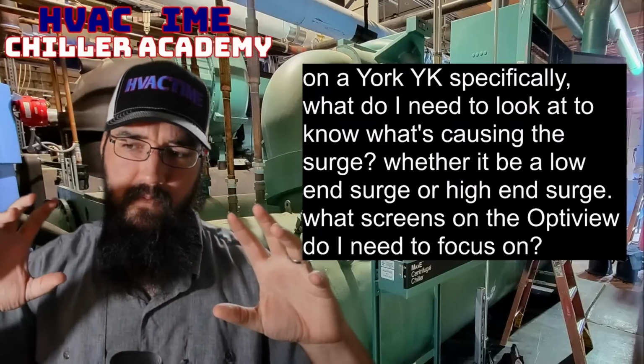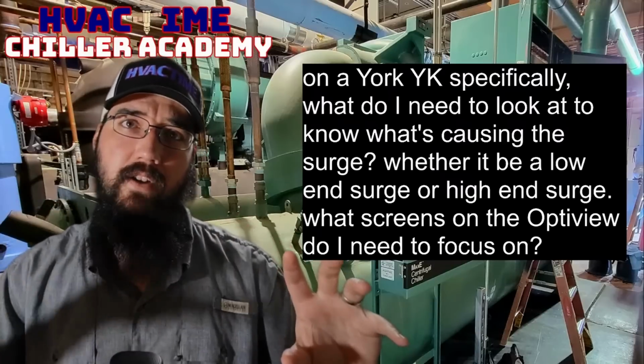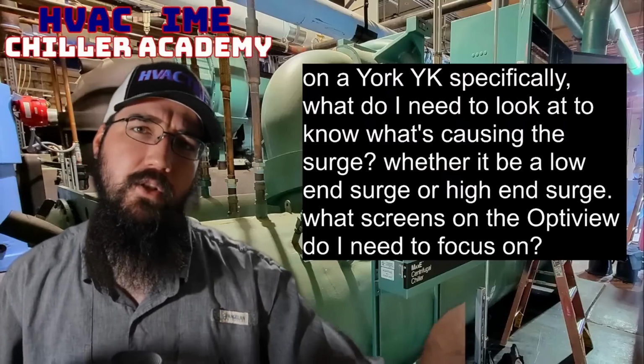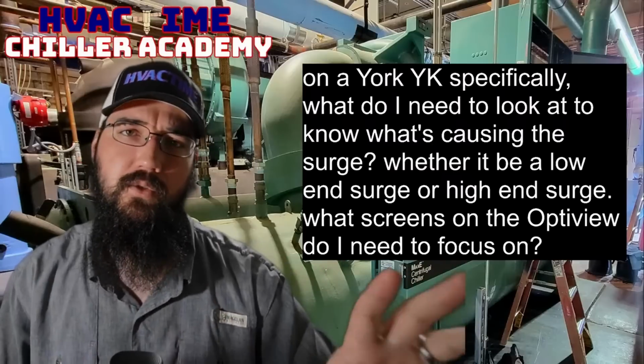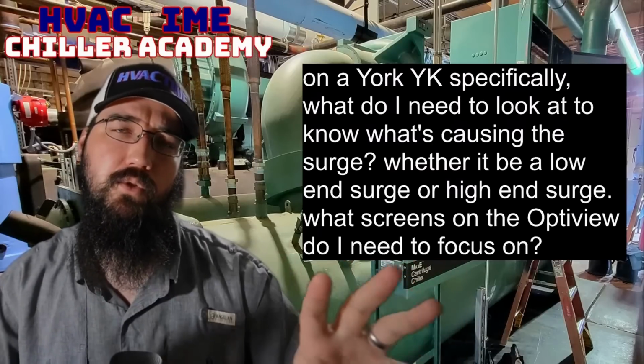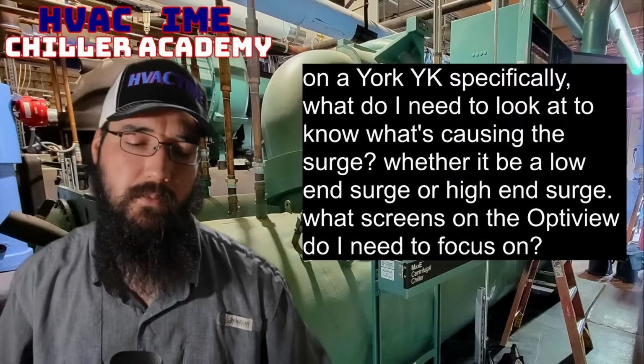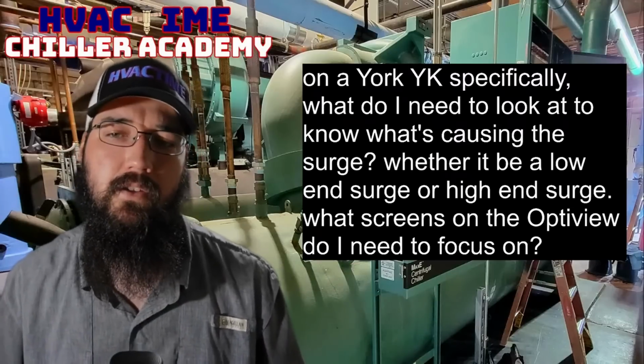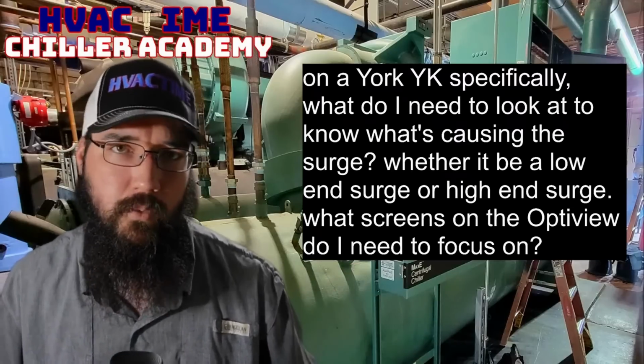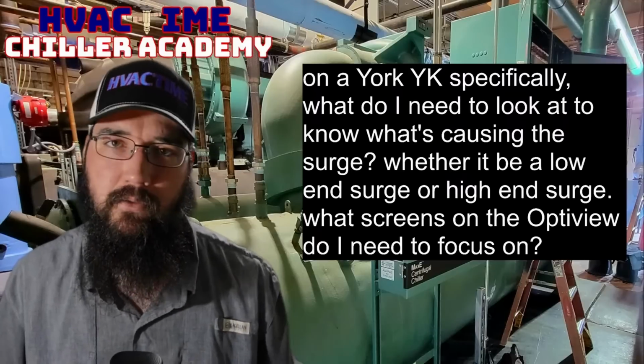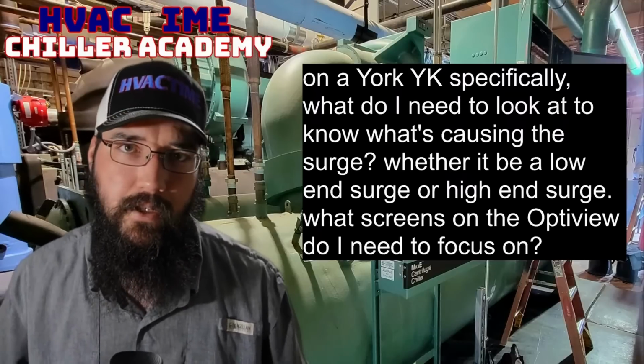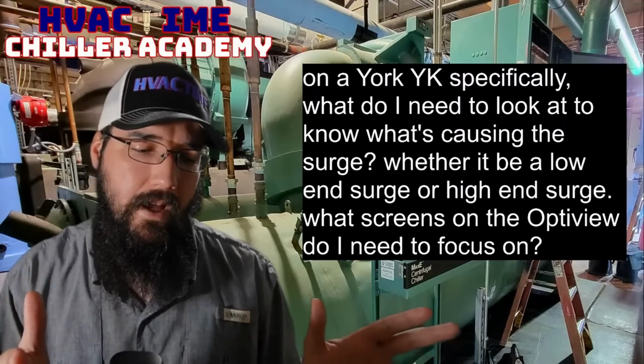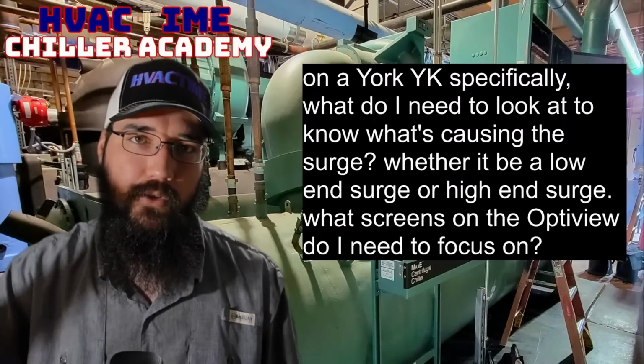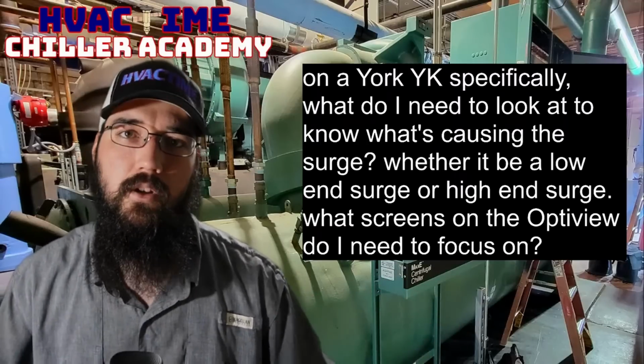Now, other than that, your evaporator and condenser screens, and maybe even your system screen, those three are going to be probably the most critical under most surge conditions, because you got to get back to the basics of, one, do we have GPM? This goes back to the very first question. Do we have GPM? Do we have proper load? Is our condenser too high? Is the evaporator too low?